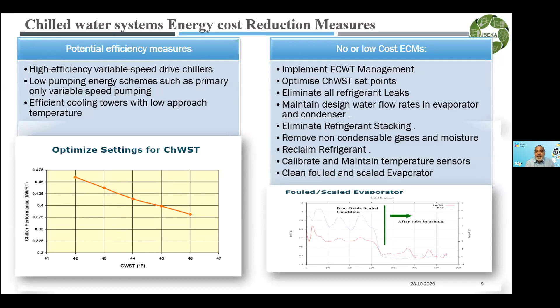Clean and fouled and scaled evaporator, you can see the difference that if the evaporator scaling or fouling happens, or condenser fouling or scaling happens, then energy consumption increases. And you can see that after cleaning, there is a substantial reduction in the energy consumption. Optimizing the chilled water temperature is very, very important, because you'll find the energy consumed by the chiller, or kilowatt per refrigeration tonnage, is decided by the chilled water set point. To understand what is the temperature requirement and set precisely the chilled water temperature.